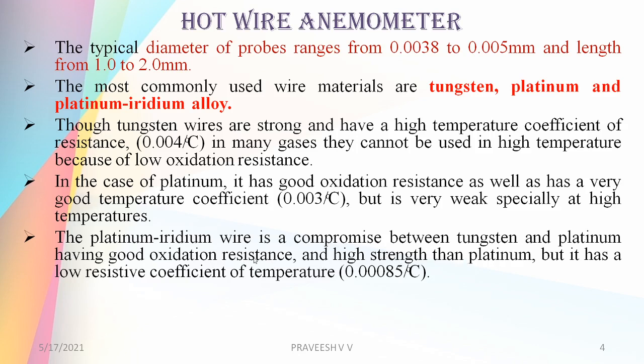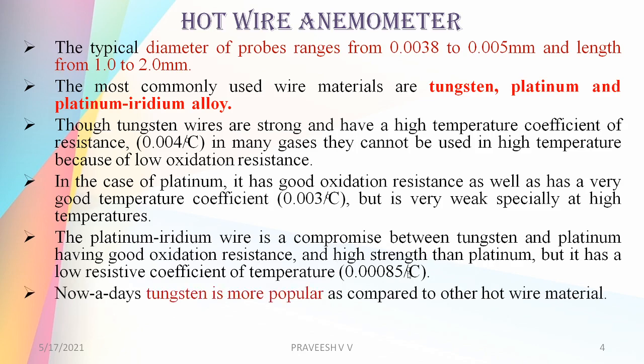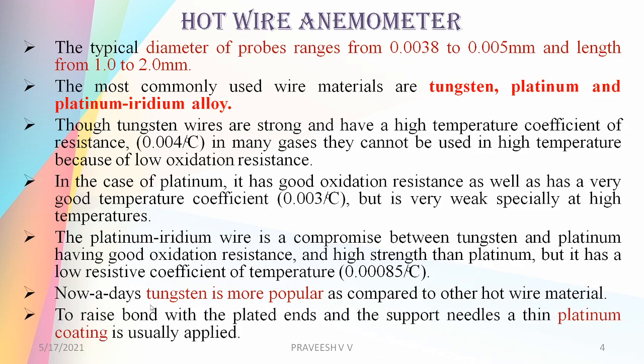Platinum-iridium has a lower resistance temperature coefficient of 0.00085 per degree Celsius. Nowadays, tungsten is more popular compared to other wire materials. Tungsten wire is used with plated ends and support needles, and a thin platinum coating is usually applied to the surface to define the sensing length.